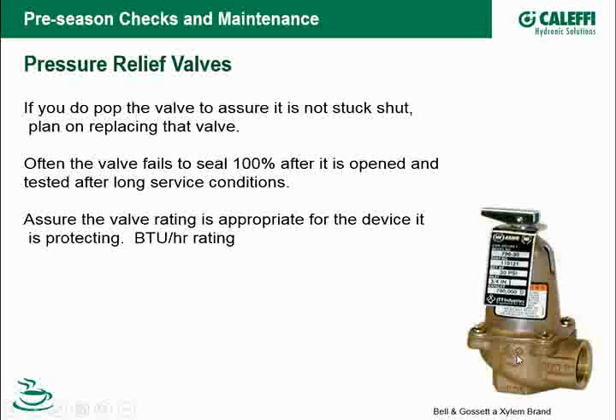I prefer this type of valve. This has a brass body in it. There are some out there that have steel or iron bodies on them that can get a little bit of rust and corrosion in them. I like the brass type better. Now, the controversy on this type of valve, when you're doing your startup check, some guys say, well, you should pop that valve to make sure that it's not stuck, so that there is an overpressurizing condition that this valve can relieve and do what it's supposed to do.